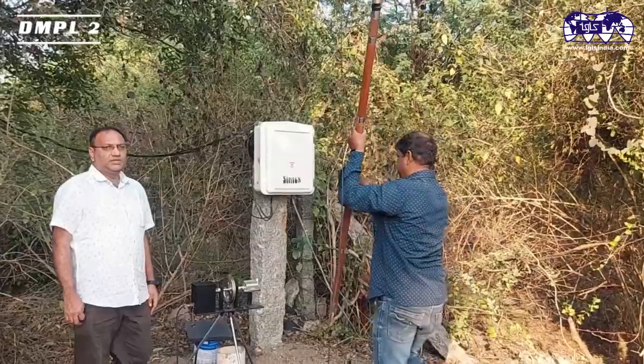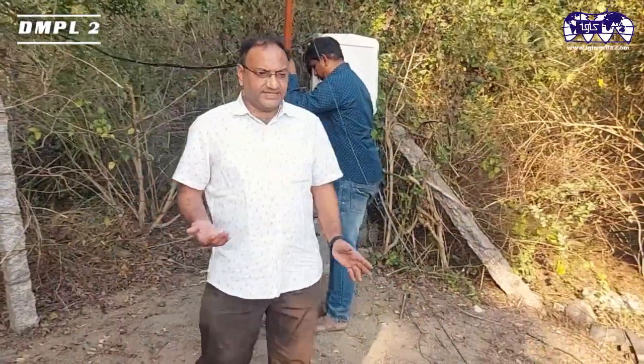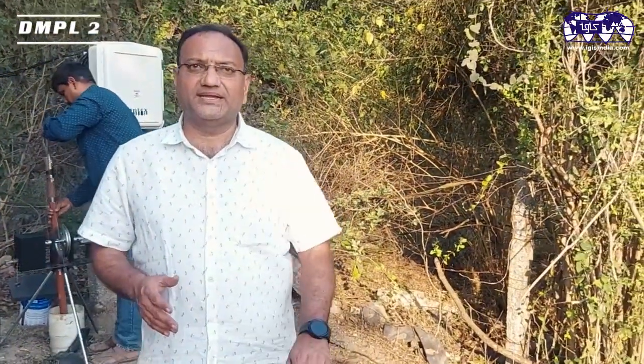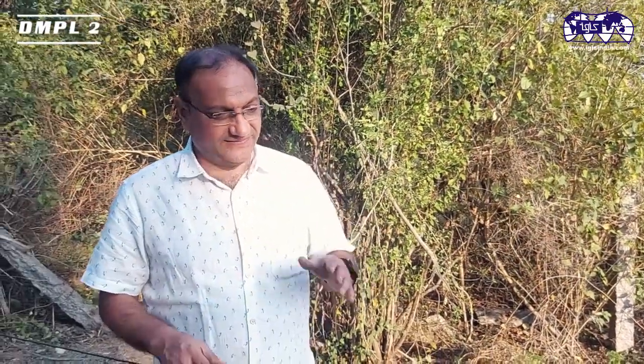Let us lower the probe. Usually logging is done two ways. One is down logging, another is up logging. The data would be the same, but it is always advised to take the up logging. The reason is, during down logging, because it is a fresh bore, there is a possibility of collapsing, there might be a chance that the probe is not lowering fast and there might be a gap. But in up logging, as you are pulling the probe, the cable is intact and straight, so the measurement is appropriate. That's the reason it is always advisable to use up logging. Down logging is just for reference.